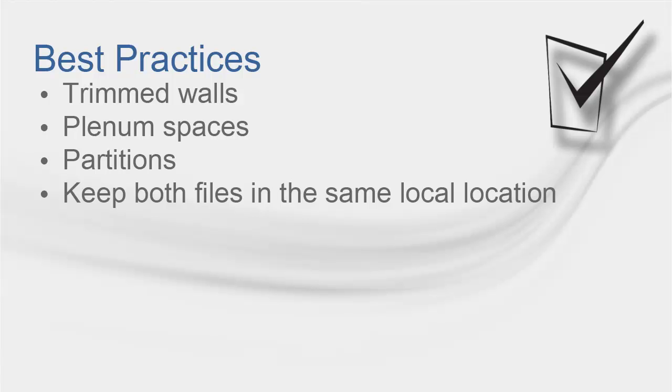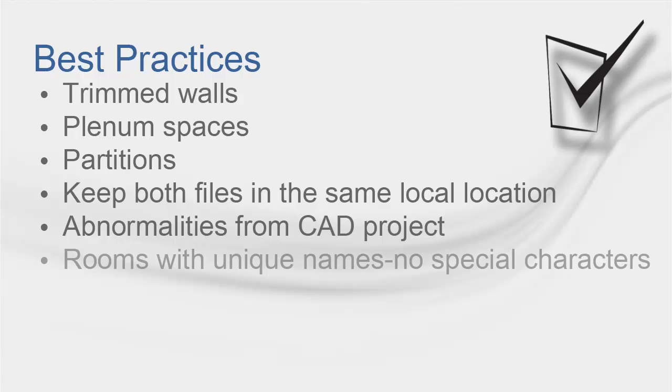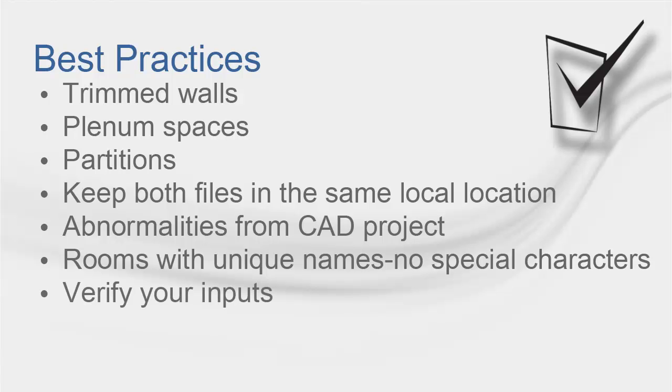Next, keep both your Trace and GBXML files in the same location in your local computer. Importing a GBXML file from a server might create some problems. Abnormalities or errors may propagate through GBXML if the original CAD project has mistakes in the drawing or definitions. Rooms should have unique names and special characters should not be used for their name. Do not use special characters to name the GBXML file nor the Trace file.